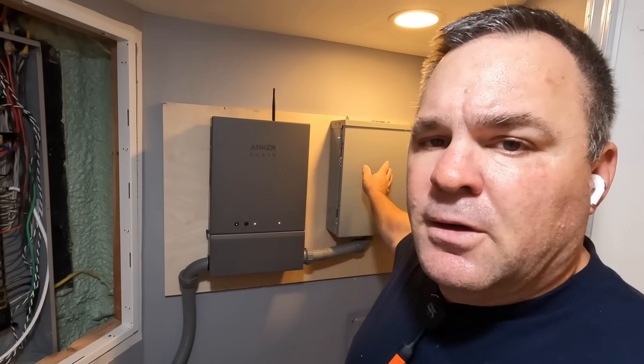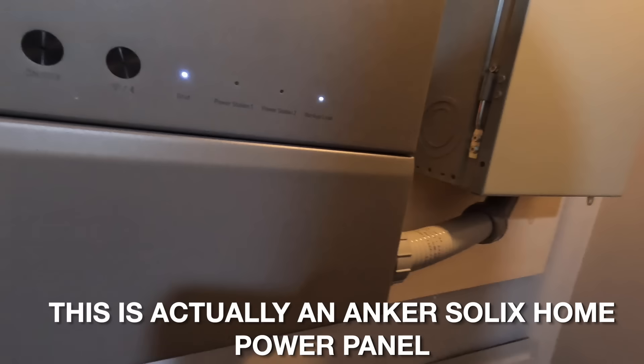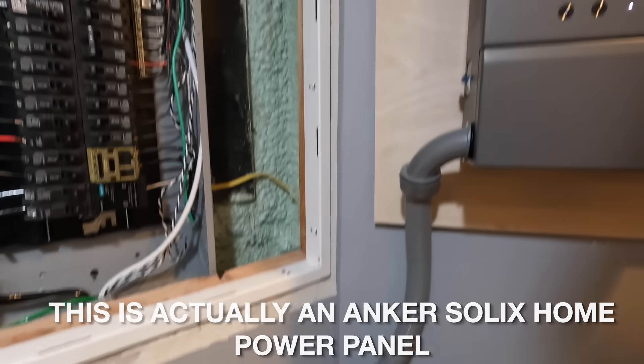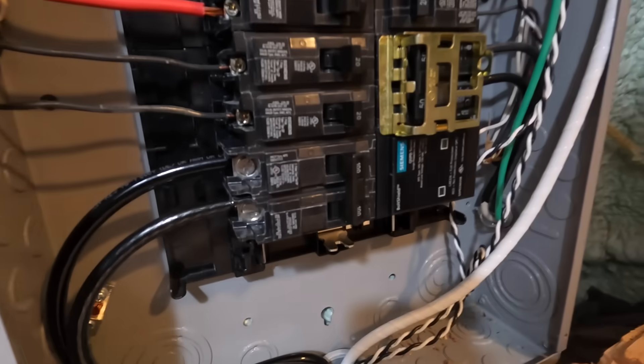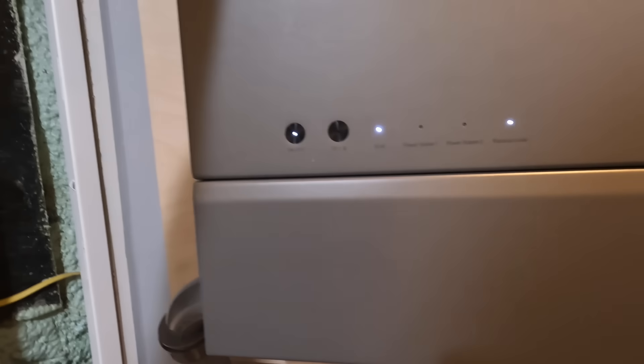I'm done for the first day. I still haven't done the branch circuits from the main breaker panel to the emergency panel, but I'll come back and do that another day. This ends the first chapter of this brand new Anker Solix — first one I've ever done — the F3800. As you can see, the control panel is lit and we're ready to go. Today we installed the 100-amp circuit breaker with number 3 copper conductors, connected the current transformers around L1 and L2, fed the transfer switch, and the transfer switch supplies the generator panel. We'll come back and finish this up in a few days.